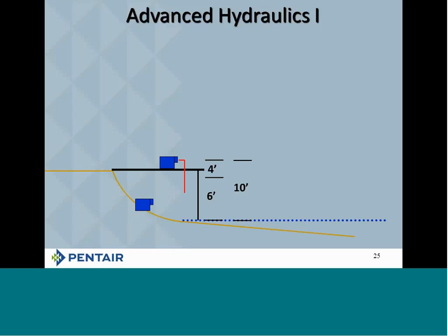So if we physically put the pump closer to the water here, you're going to notice that once the water comes back and we're not around, we now have an above-ground pump that is submerged. The secret here, they don't work very well when you submerge an above-ground pump. So we really need to leave the pump where it is on the dock there. Okay? The problem comes in, if you look real carefully, where's the suction pipe? Out of the water. So now we have to add some suction pipe.